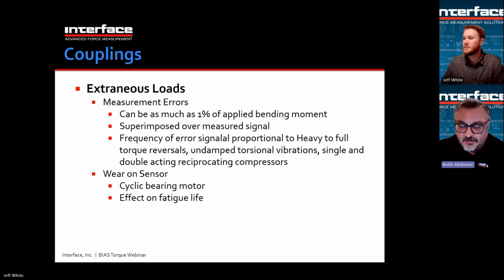Again, wear on the sensor is another issue. Bending of the shaft, if you have bending and then it rotates, it's just like bending it back and forth a bunch of times, can definitely prematurely wear out the sensor. Also bearing loads. A bearing style sensor has bearings that are not at all intended to do anything but allow the shaft to rotate inside the housing. And so if you have side loads or bending moments that create bearing loads, those are going to wear the bearings out. That's the last thing we want, because it's not a rebuildable bearing that you just buy a new bearing and replace. It means the entire torque sensor has to be rebuilt, recalibrated, remanufactured. So use couplings. Moving on.